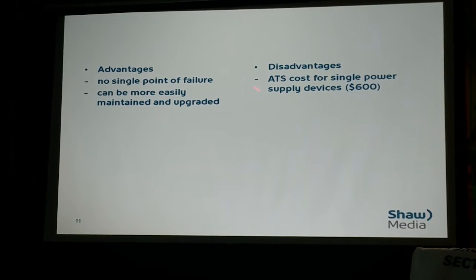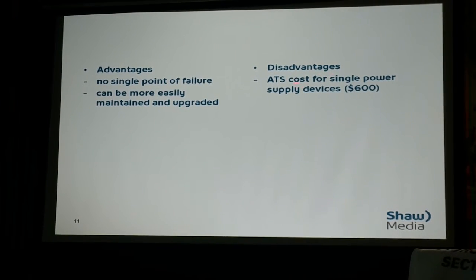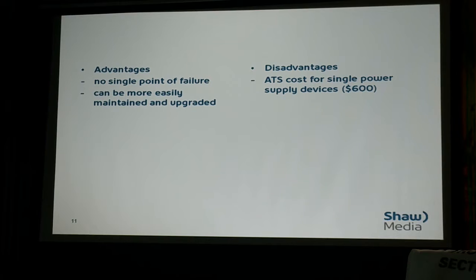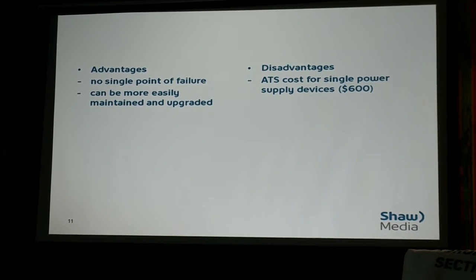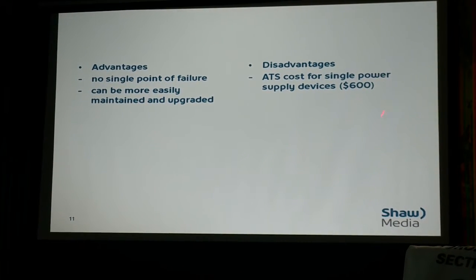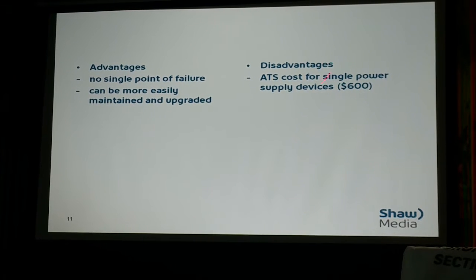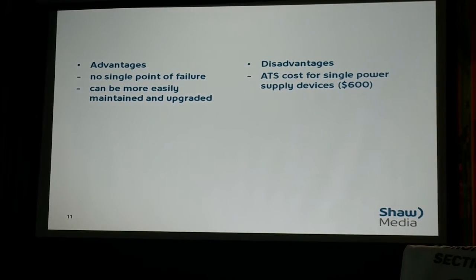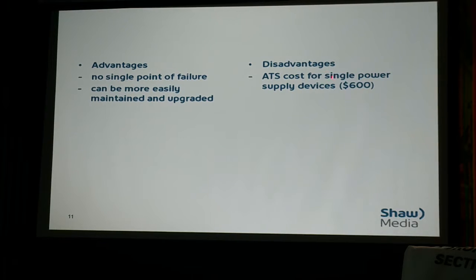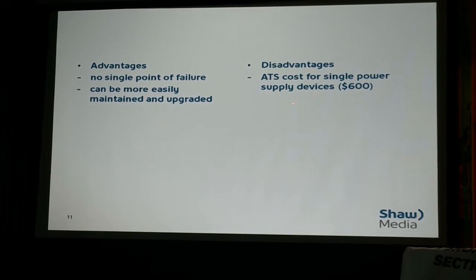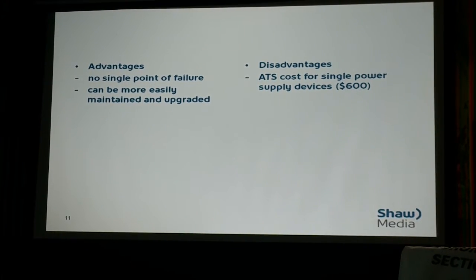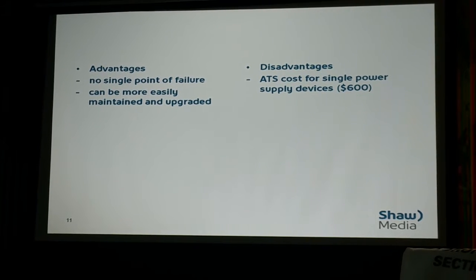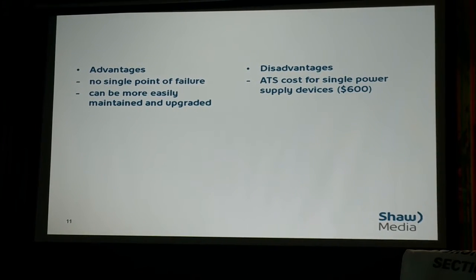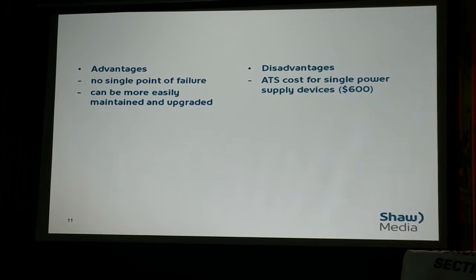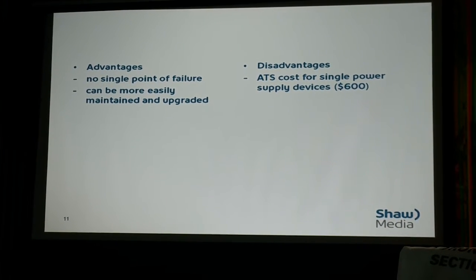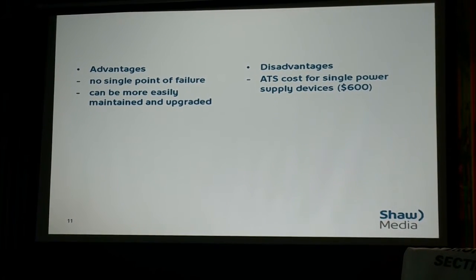Those little ATS units cost us roughly about $600 each. So when you're speccing out a new piece of equipment, you have to decide if a second power supply is more cost effective than a single power supply device. There are actually 8 ports on each one, so you can bring the cost down a bit. Each ATS has 8 plugs, so you could power 8 single power supply devices with it.